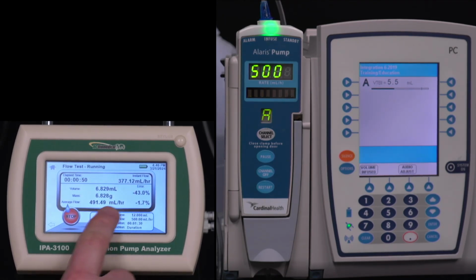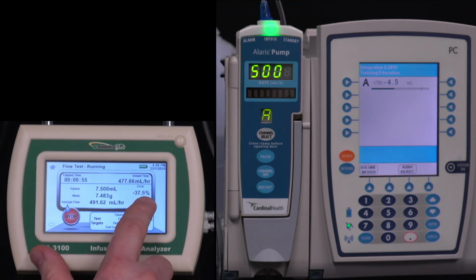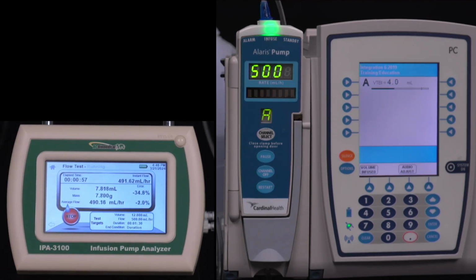And we'll see the percent error shown as it runs. You'll notice that the volume percent error is pretty high. Again, we had it set for 12 milliliters, so it hasn't gotten anywhere near 12 milliliters yet. So that percentage of error should drop as it gets closer to the target. One thing I'll say as the test is running: when the infusion pump gets done, it's going to go to a KVO mode, keep vein open, a really low flow rate. So for this test, I want to make sure that I stop the test when the pump stops and goes to that KVO mode.